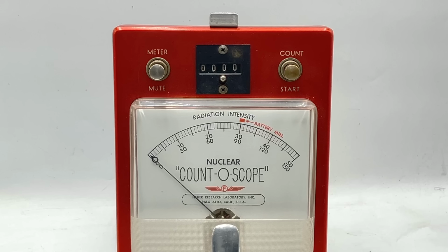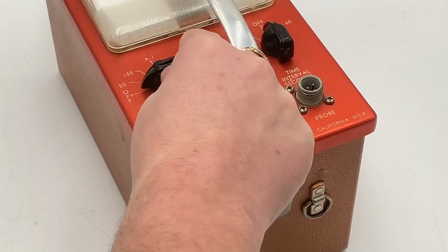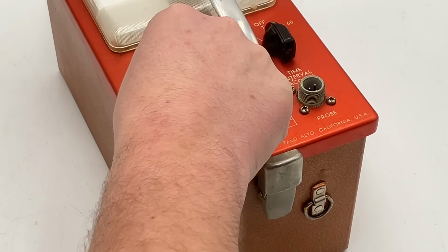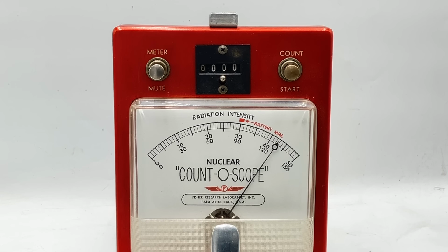Moving forward, we have a readout dial, aka the linear rate meter, which is not marked in milliroentgens per hour, but rather 2 generic relative intensity scales of 0 to 50 and 0 to 150, which roughly correspond to 0 to 0.1 and 0 to 0.3 milliroentgens per hour, respectively. We'll also notice the battery minimum marking on the scale. When the left-hand knob is set to the A1, A2, or B1 positions, if the needle does not climb beyond this mark, then that battery group needs to be replaced.